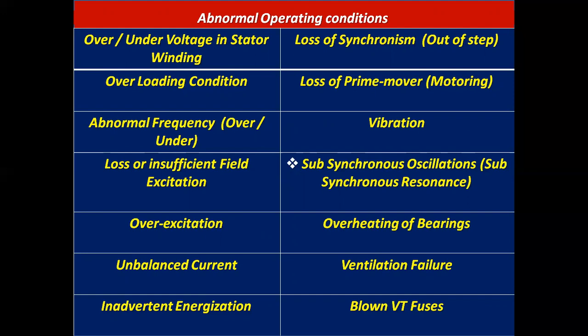Again, I repeat, abnormal operating conditions: over or under voltage in stator winding, loss of synchronism, that is out of step, overloading condition, loss of prime mover, that is motoring, abnormal frequency, over or under, any sort of vibration, loss or insufficient field excitation, sub-synchronous oscillations or sub-synchronous resonance, overexcitation, unbalanced current, inadvertent energization, overheating of bearings, ventilation failure, blown VT fuses. These are all the abnormal operating conditions.